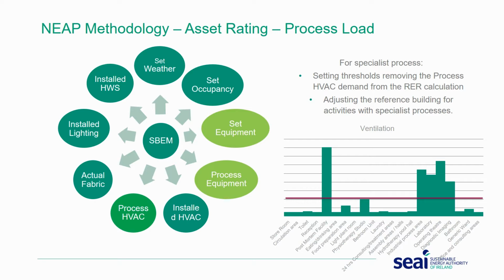So we are comparing you to a reference building, and Sean mentioned earlier that the performance of the reference building in terms of cooling is 4.5 seasonal performance of the chiller, but the system seasonal performance is 3.6, which is equivalent to chilled beams. So it's a very efficient cooling system. Whereas process loads, operating theatres or industrial clean rooms have specific requirements in terms of the services within them. So we're changing the reference building, or the parameters, for specific process conditions, so that you'll be able to compare yourself like for like, rather than having to compare yourself to the chilled beam system.